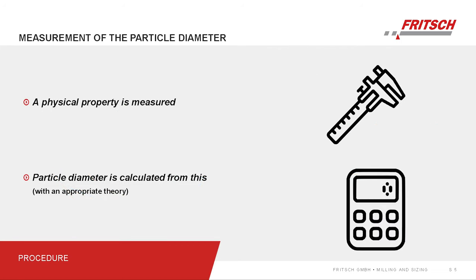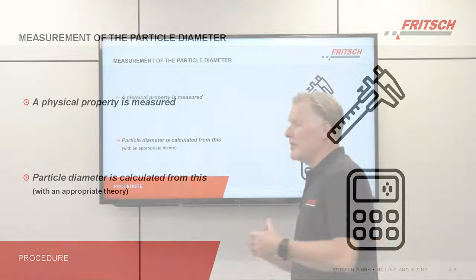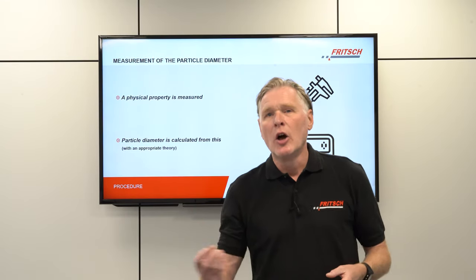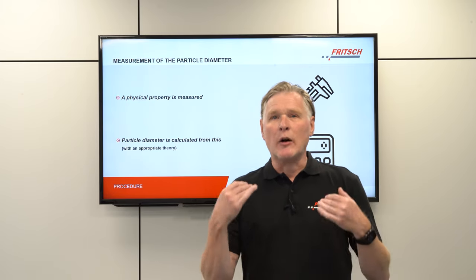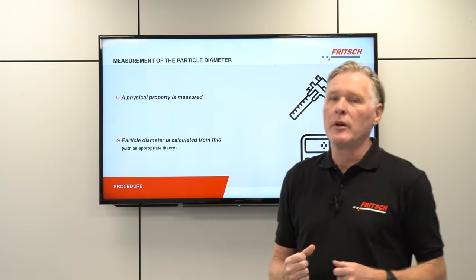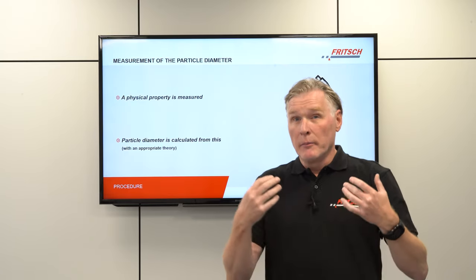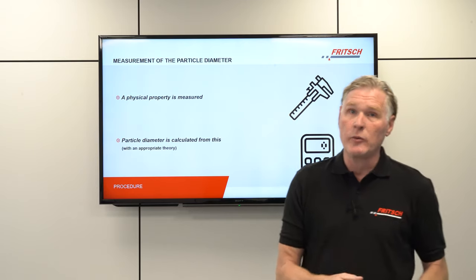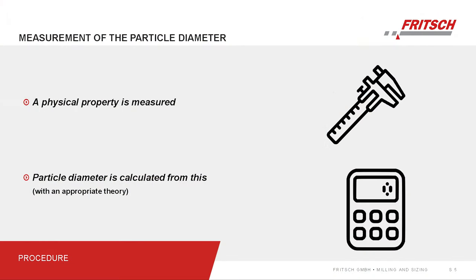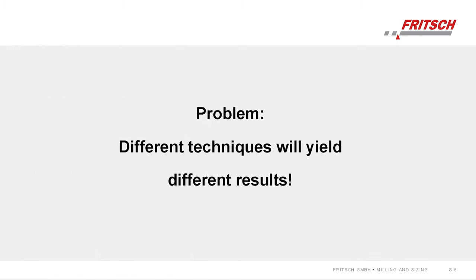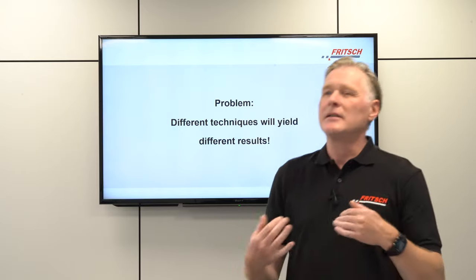Typically we measure some physical property — for example the sedimentation speed of particles in a liquid column, or the attenuation of a sound wave travelling across a sample. From this physical property we then calculate the particle diameter distribution using an appropriate theory. The general problem is that when you use different techniques, you will get different results.